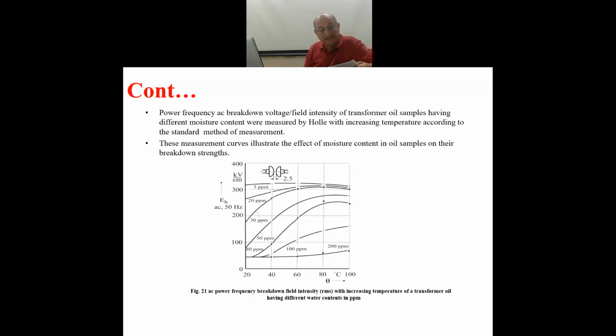The measured electric strength of highly purified mineral oils could be to the tune of 1,000 to 4,000 kV per centimeter. I mean, for very highly purified oil in utmost clean and best possible conditions, people have measured the breakdown strength of oil to the order of 1,000 to 4,000 kV per centimeter.